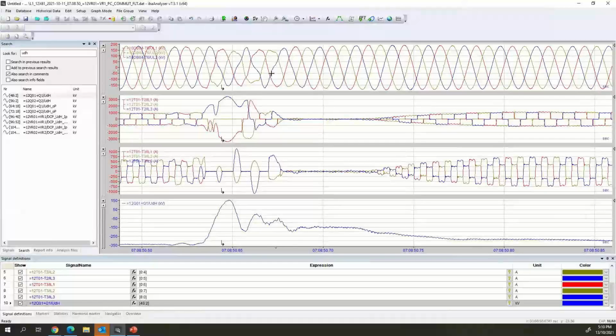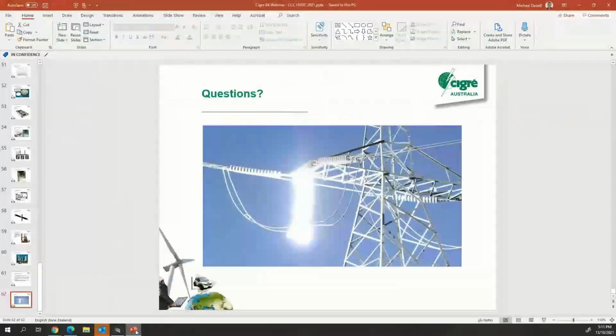Awesome. We've had a few more questions. Does deionized water cause any corrosion issues? I think it's actually better. We don't seem to have too many issues with corrosion. There is an issue where you can get build up, but that's due to the DC voltage. The valve cooling water has a DC voltage put across it, and that causes corrosion where the current goes from the metal into the water, and build up where it goes from the water back into the ground or wherever it is. You can have these build-ups occur, but it's very minor.